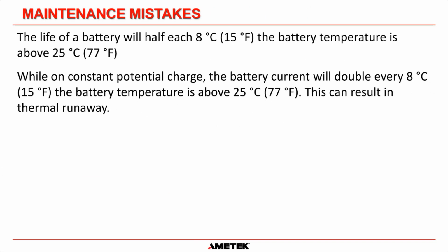And conversely, the life of a battery will halve for each 8 degrees Celsius, or 15 degrees Fahrenheit, that the battery temperature is above 77 degrees Fahrenheit. Now, that is over a prolonged period of time. So we're not saying that if the battery goes up to 100 degrees Fahrenheit for 2 days, the battery life is halved. That's not what we're saying. But if it is 100 degrees Fahrenheit constantly, then that will reduce the battery life by half. Actually, it's not even 100 degrees. It is 77 plus 15, so it would be 92 degrees Fahrenheit. You will lose half of the life of your battery.